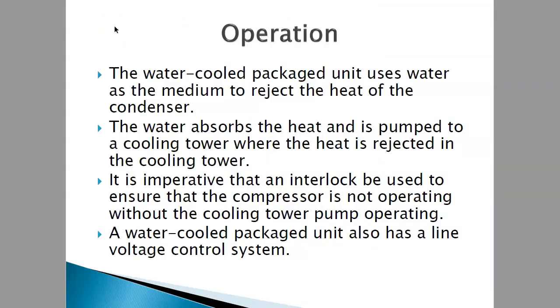Okay, this is the operation of water cool package unit, where you use water as a medium to reject the heat of the condenser, and then it's being pumped to a cooling tower, where the heat is then rejected in the cooling tower. To ensure that the compressor is safe, it has an interlocking system, which means the compressor will not work without the cooling tower pump being operated. If not, the compressor will only compress air without the water. Water cool package unit also has a line voltage control system.